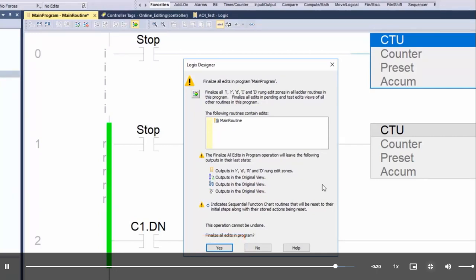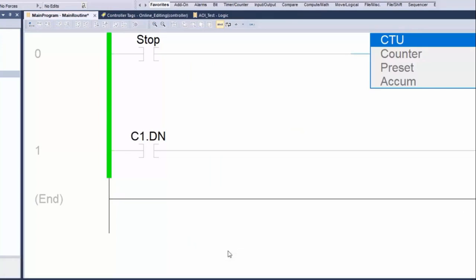By selecting Finalize All Edits, we are going to finalize all edits in all edit zones of all ladder routines in the selected program, and all edits in all pending edits and Test Edits views of all other routines in the program. Clicking Yes, Logix Designer will accept any pending edits, download the edits to the controller, assemble all edits, and begin executing assembled edits if the controller is in run mode. The Finalize All Edits feature enables us to reduce the steps required to go from changes to running code.